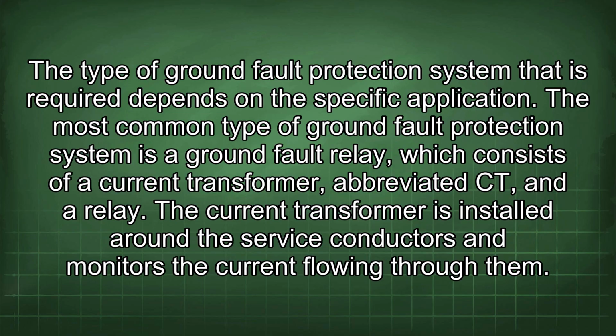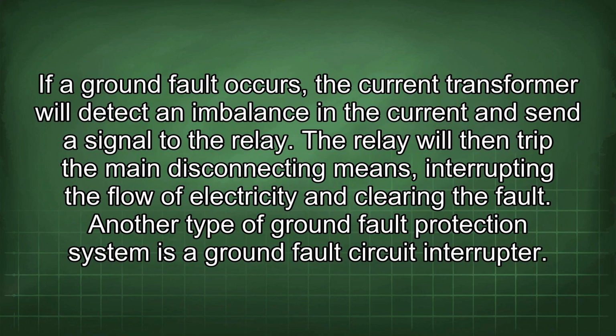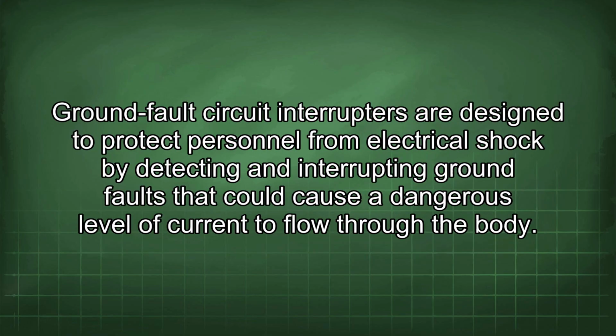The current transformer is installed around the service conductors and monitors the current flowing through them. If a ground fault occurs, the current transformer will detect an imbalance in the current and send a signal to the relay. The relay will then trip the main disconnecting means, interrupting the flow of electricity and clearing the fault. Another type of ground fault protection system is a ground fault circuit interrupter. Ground fault circuit interrupters are designed to protect personnel from electrical shock by detecting and interrupting ground faults that could cause a dangerous level of current to flow through the body.